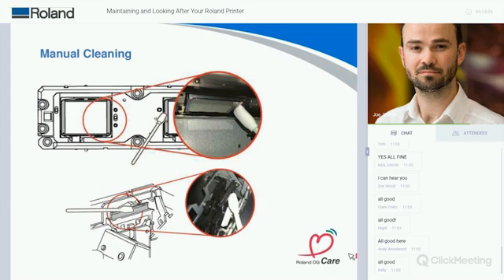These ones, again, as per usual, you're going to want to be cleaning around the edge of the print head. So you don't want to be touching the surface of the head unless you're having any print quality issues. If you speak to our tech support team, there is a possibility they may ask you to clean the surface of the head, but it's very unusual. I recommend avoiding doing that off of your own back, because that can make things worse. It's generally just kind of a last resort kind of thing.